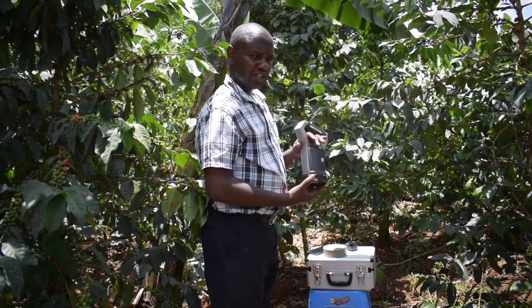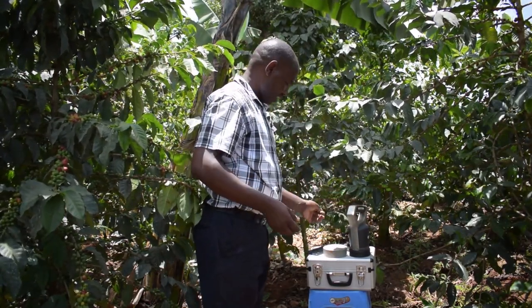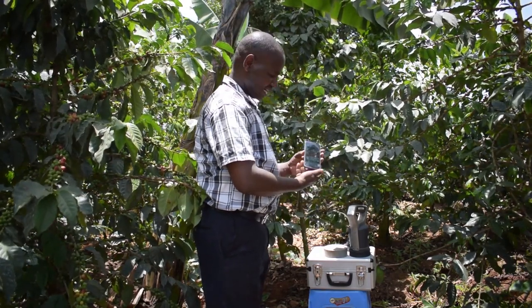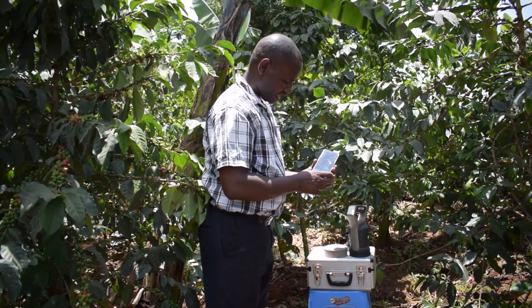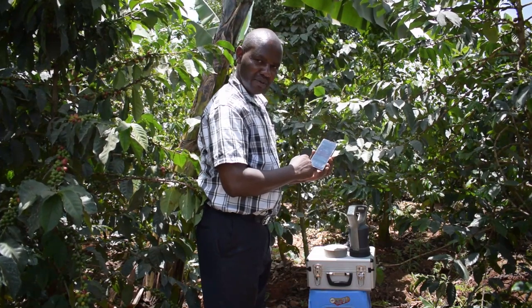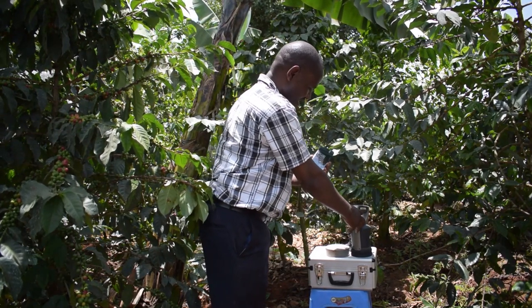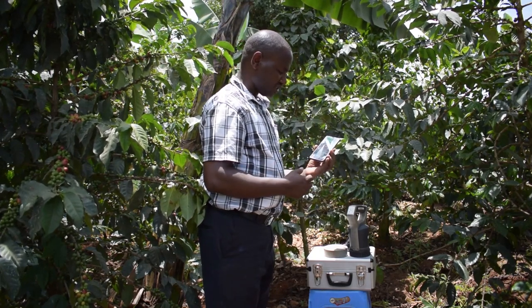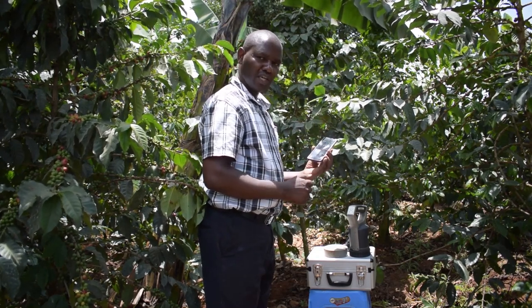The calibration is used to erase any information from the previous sample. Once we have connected the scanner and the machine, the scanner is controlled by the application. We are going to press the scan button first to scan the white side, and after the white side, we will scan the yellow side to make sure that this machine is in proper and good working condition before we get into the sample.